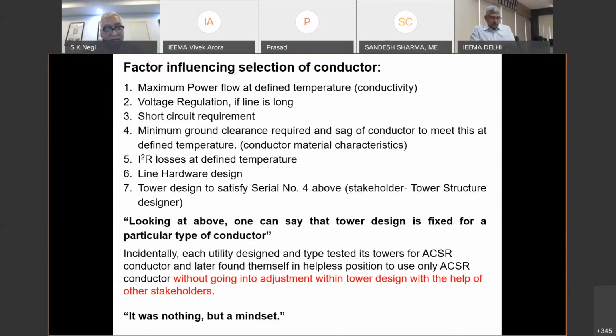And all these manufacturers' R&D and capital venture will not invest money unless they see the prospects of a particular type of conductor coming into the market and acceptability in the utility. And we continue to use ACSR Moose conductor as a tradition. One has to note that it has very limiting factors as far as power flow is concerned, due to the surge impedance loading, as well as it starts losing strength above 90 degrees centigrade temperature operation.